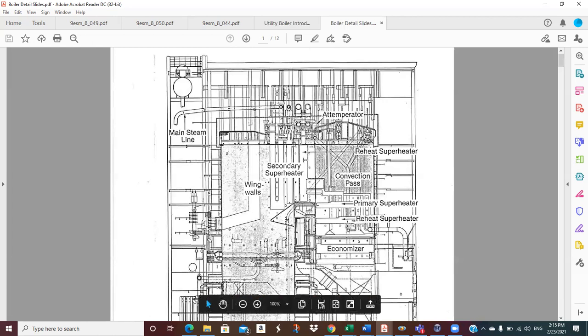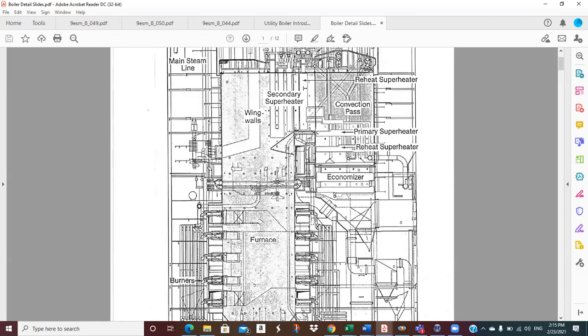Like on the main steam, they would do it between the primary superheater and the secondary. So you would put it in between, and then the steam goes through the secondary superheater, which gives it an opportunity to evaporate any water that you sprayed in to protect your turbine. So they're very particular about where they place these attemperators. They put them on the reheat steam as well, but they're going to put it before the last reheat superheater. So again, they can be sure that they evaporate any liquid, because you don't want a bunch of liquid flying through those reheat lines going back to your turbine or your main steam lines. You know, furnace area, we're showing burners stacked.